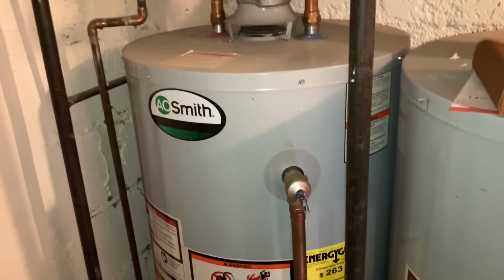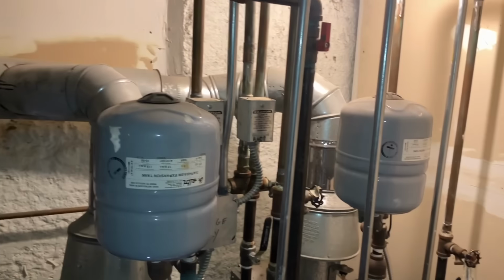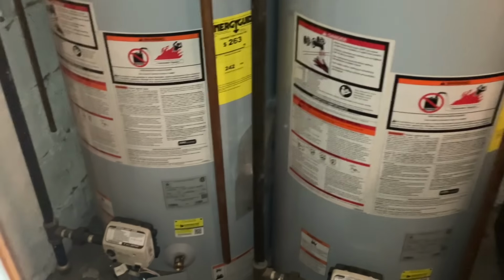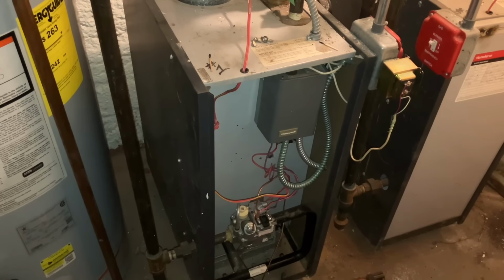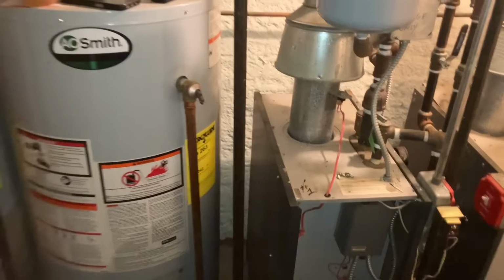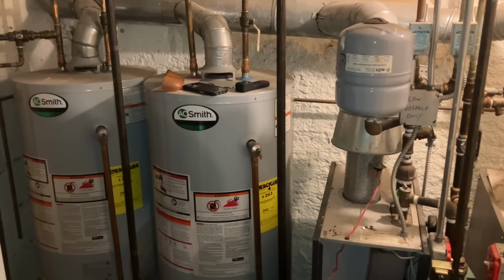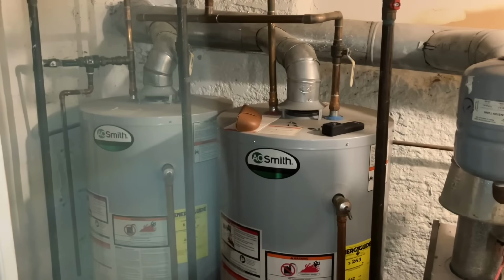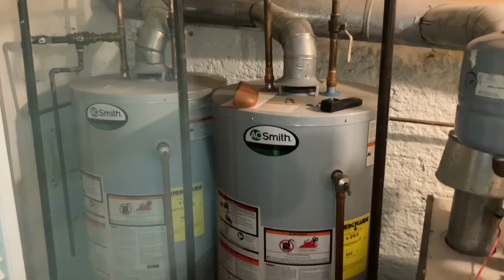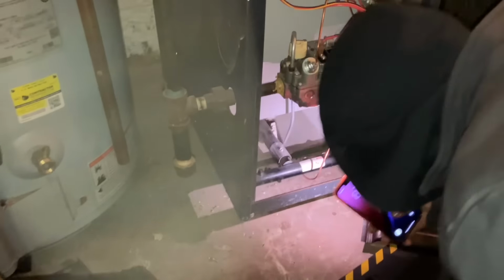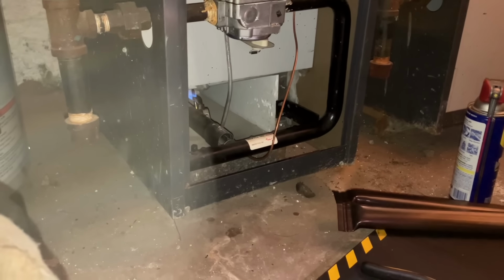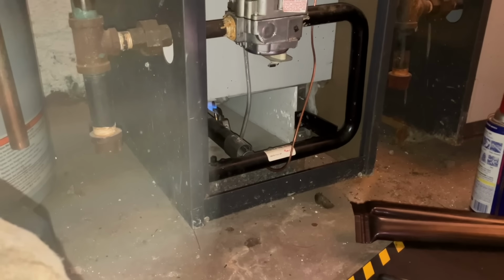I wonder where the combustion air is for these. You know, as weird as all this is, there's no combustion air. You have 40,000 BTUs, another 40,000 BTUs, probably 80 or 100,000 BTUs each, 200,000, and then 280,000 BTUs here in this. I guess it's a louvered door. I guess it makes it okay, but people often neglect combustion air. And think about it. If you consider a wax candle, it releases roughly 80 watts of heat. 1 watt equals 3.4 BTUs an hour. So 80 watts times 3.4 and change is 270 BTUs per hour.